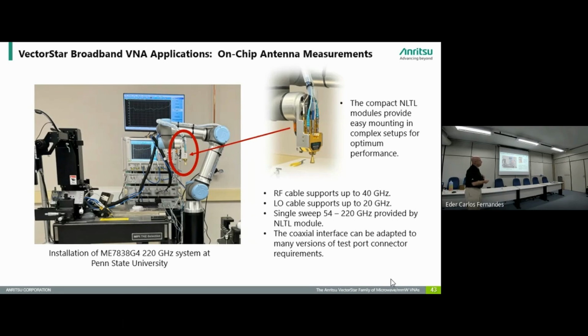We unhooked it because we knew that cable was going to be longer, since it had to come up the arm, bundled back here, and into the module. Even if I could put that cable there, there would be a lot of loss, so measurements up to 54 gigahertz would be seriously degraded, and they're not necessary since this was WR6, D-band. So the RF cable going to this module runs at 40 gigahertz, and gets multiplied up from there.